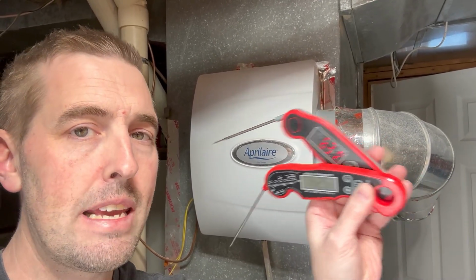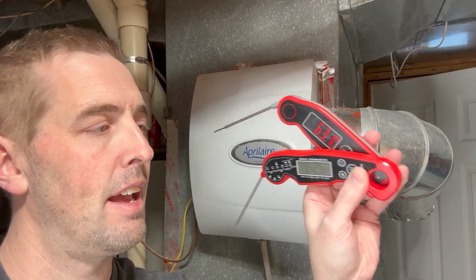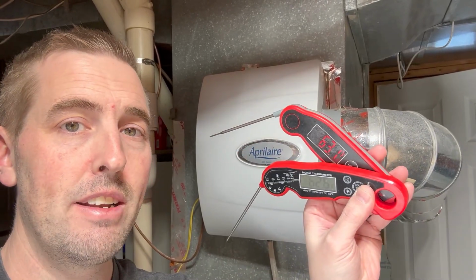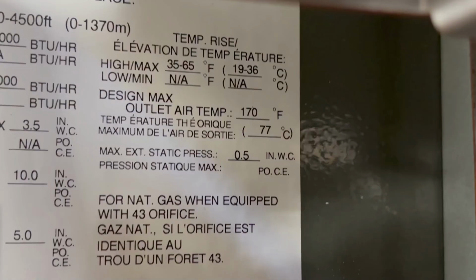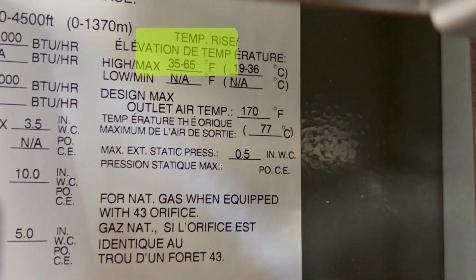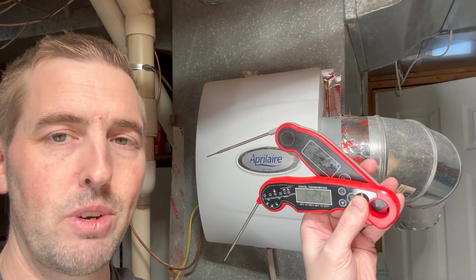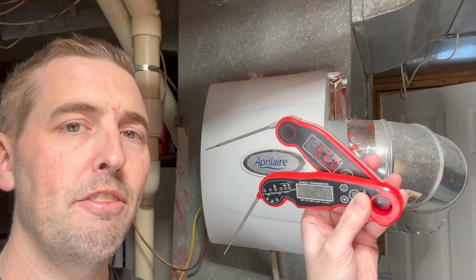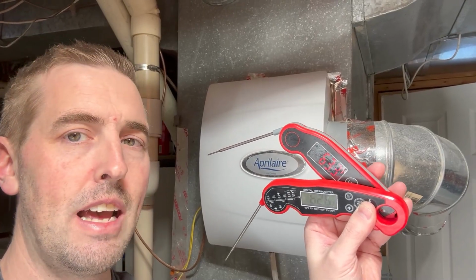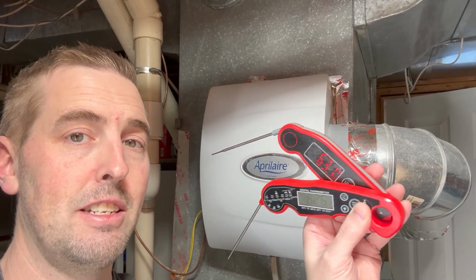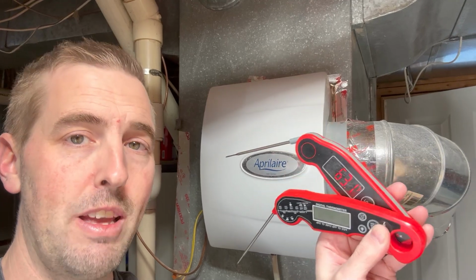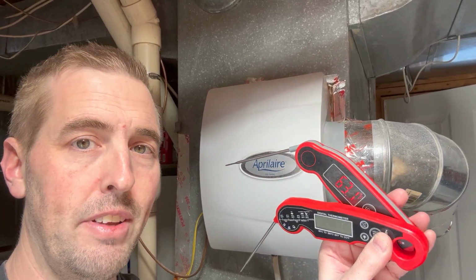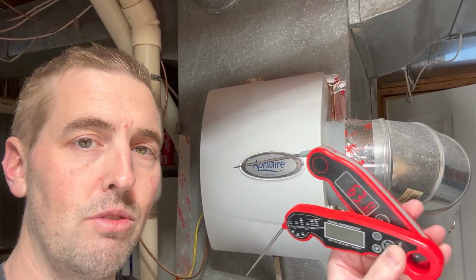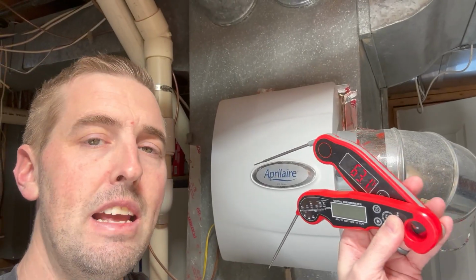We're going to be running in heat mode because it is cold outside, and so the furnace is rated with a maximum delta of 65 degrees Fahrenheit, and that's going to differ based on different furnaces, but that's what ours is. And so if the difference between our inlet and outlet side of the furnace exceeds 65 degrees Fahrenheit, it's going to trip a limit, burners are going to shut off, it's going to have to cool, fan will continue to run, and then overall it's just inefficient.